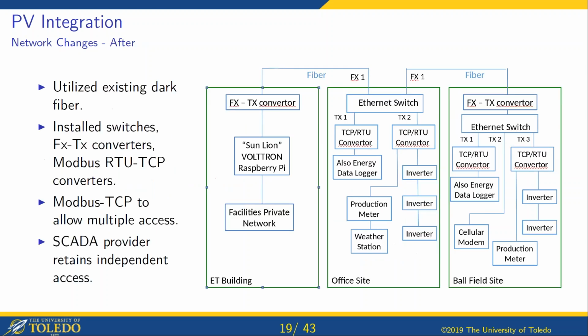But there was conduit there with a fiber, which we were able to bring in, install some Ethernet switches, and convert things over from Modbus RTU to Modbus TCP, which allows us to have multiple access to it, so we're not interrupting anything that they do. And now we're able to bring that information in directly.